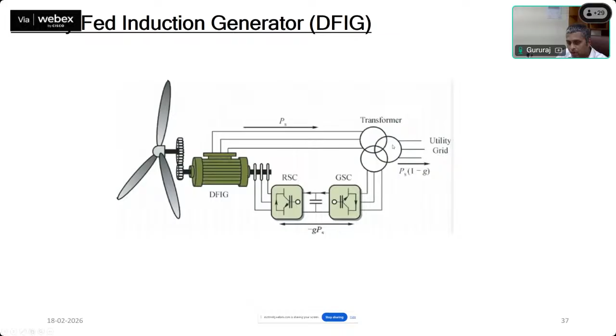And apart from the hardware techniques that we have discussed, we also have software techniques. The software solution, in a nutshell, is quite simple. The idea behind this software approach is to counter the magnetizing component of the flux, which is responsible for the increased voltage seen at the rotor circuit. So you already have the back-to-back converters and the DC link capacitor. You just inject the opposite magnitude of current, or demagnetizing current, into the grid via this converter, so that the impact of this magnetizing component of current on the grid and on the converters can be avoided.